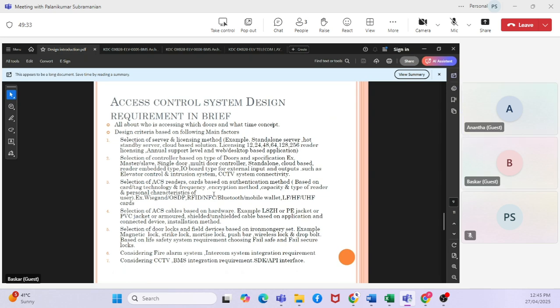The fourth point is also very important for the data center perspective - you have to go with low smoke, zero halogen cable. For indoor cables, the outer sheath is a PVC jacket material. Low smoke zero halogen, as the name implies, doesn't impact the fire stage - it will not explode or aggravate the fire. So you must choose cables with low smoke zero halogen outer sheath for access control, BMS, and whatever systems you are using. If you're going outside the building, use PE jackets.